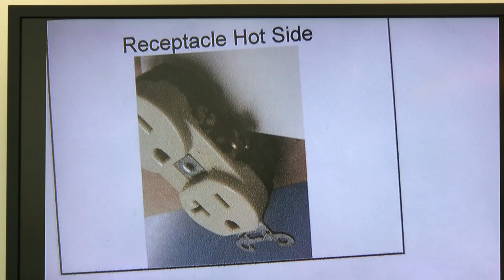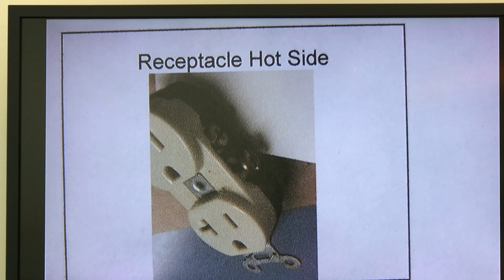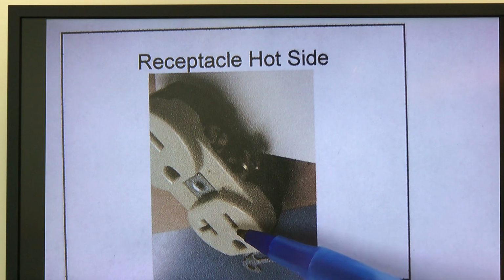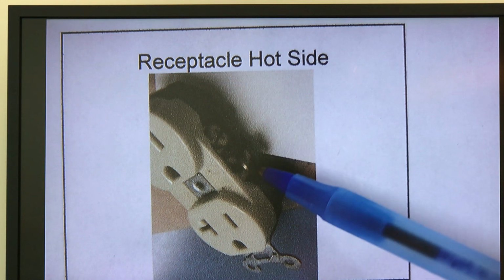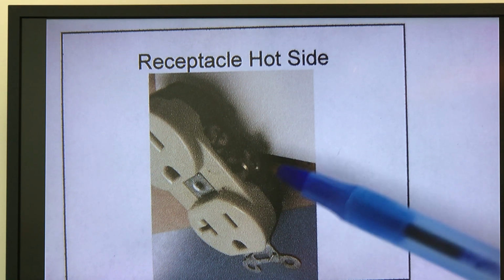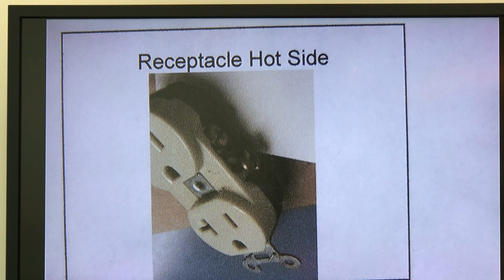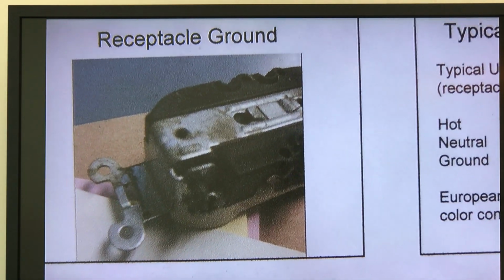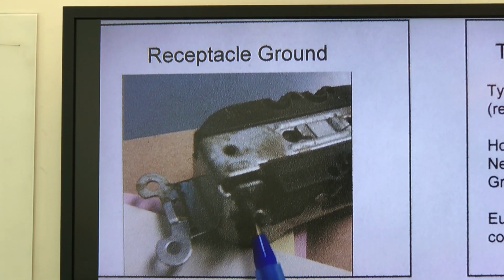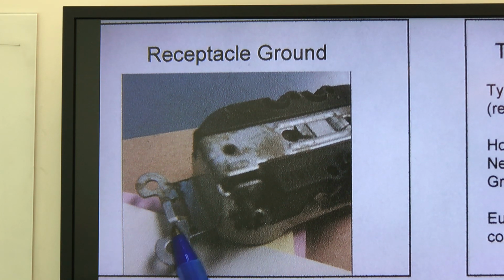What we're showing over here is the receptacle's hot side. Notice that the orientation is the same, even though the view is slightly different, because now we're looking at the connections to these little shorter pegs. Notice that this is now brass colored. It may not show up particularly well when you watch the video, but this is the brass colored connection. And if we take a look at the receptacle body itself, here's that screw that we saw ahead of time. It still has a little faint patina of green, but you'll notice that this body right in here, all of this is a single piece electrical.